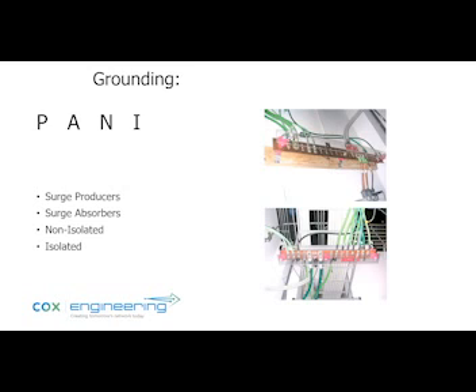Now with the grounding, some companies use what's called a PANI configuration on a master ground bar. So all the equipment is grounded—the racks, the frames of the chassis equipment, etc.—and you try to have it all go to a master ground bar typically. And if you can, some companies don't do this, but if you could arrange the surge producers and absorbers, non-isolated and isolated, on that ground bar, then that's what you need to do.